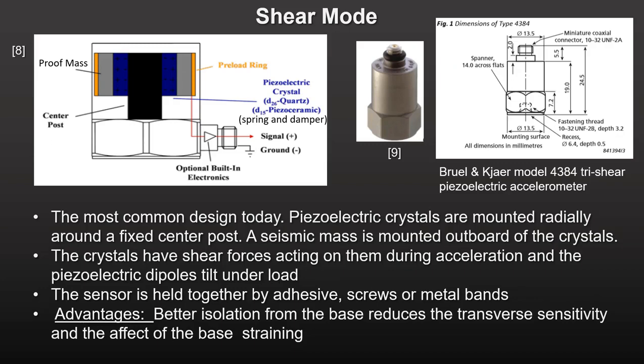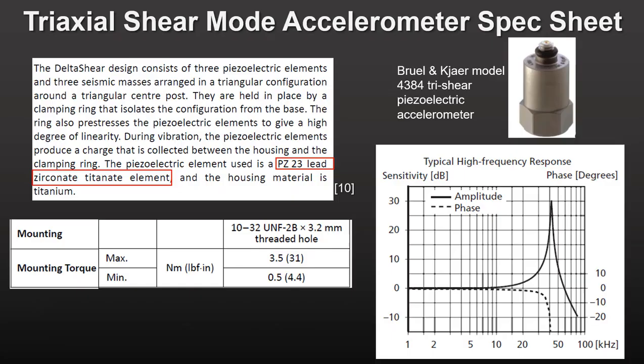In shear mode, the piezoelectric crystals are mounted radially around a fixed center post, with a seismic mass mounted outboard of the crystals. The crystals have shear forces acting on them during acceleration, and the sensor is held together by adhesive, screws, or metal bands. In a tri-shear sensor, three elements are positioned at 120-degree angles around the center post. The shear mode design isolates the crystal from base strain inputs while still providing the same degree of sensitivity as the compression mode design. As such, most piezoelectric accelerometers sold today use shear mode.